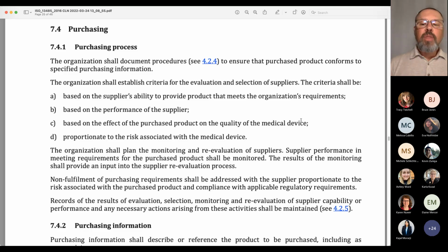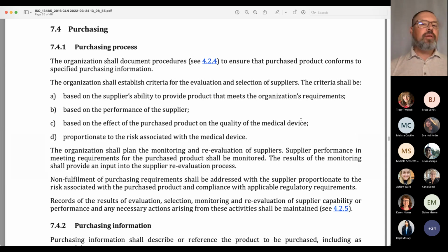You can also disapprove or disqualify a supplier. If their performance is bad enough that you no longer wish to use that supplier, then they can be marked as disqualified. And one of the reasons why you would want to mark a supplier as disqualified instead of just simply pulling the business and moving it somewhere else is that you want there to be that record in your quality system that the supplier performance was so bad that we chose to no longer do business with them. Because a year from now, 5 years from now, different people in different roles assessing the supply base may not know the history of that supplier and might inadvertently reintroduce them as part of the supply chain. So that's why we keep that disapproved status. There are other types of status that you could include in your procedure, but those are the 3 main ones that I think are probably most relevant for today.